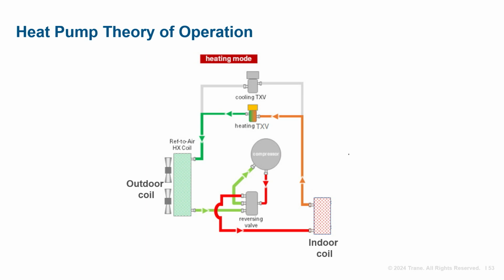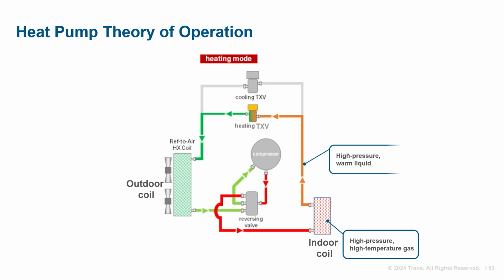In this process, heat energy is rejected from the high-pressure, high-temperature gas. As the high-temperature gas moves through the indoor coil, the refrigerant begins to subcool. In this process, heat is rejected and the state of the refrigerant begins to change. The result of this change is a high-pressure warm liquid. The high-pressure warm liquid now makes its way to the outdoor metering device. In this step, we see the direct expansion process take place. The subcooled refrigerant is forced through the outdoor TXV, where the direct expansion process instantly changes the state of the refrigerant. The refrigerant begins to boil and change state once again. This process forms a low-pressure, low-temperature gas.